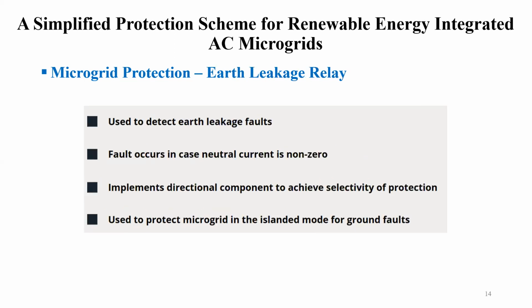Then we have the earth leakage relay. The earth leakage relay is used to detect earth leakage faults. The fault occurs in case the neutral current is non-zero, and this relay implements a directional component to achieve selectivity of protection, and is used to protect the microgrid in islanded mode for ground faults. That is important. So if there is a ground fault, this is the relay that acts.